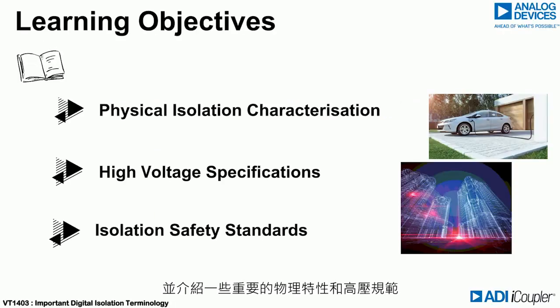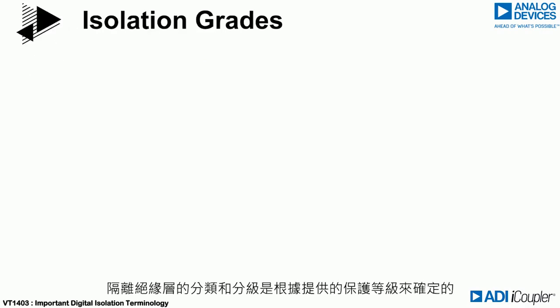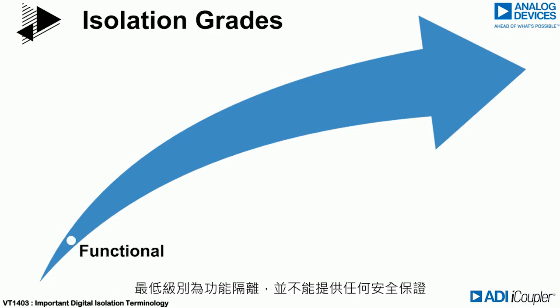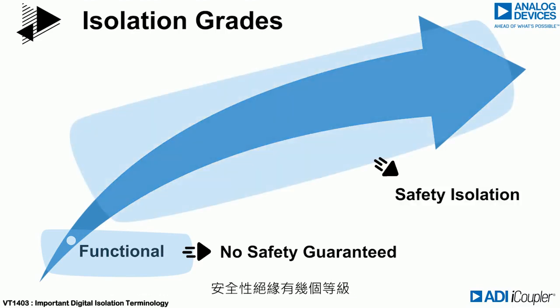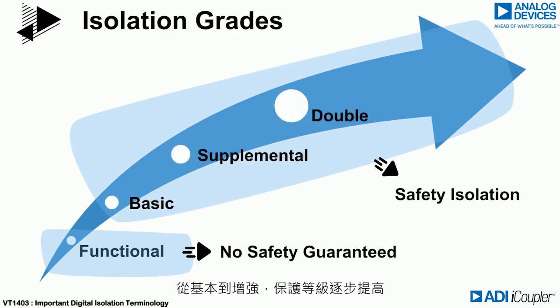We will review the important physical characteristics and high voltage specifications. Insulation is categorized and graded based on the level of protection offered. The lowest level is functional isolation, which doesn't offer any guarantee of safety. Safety insulation has several grades offering increasing levels of protection, from basic up to reinforced.